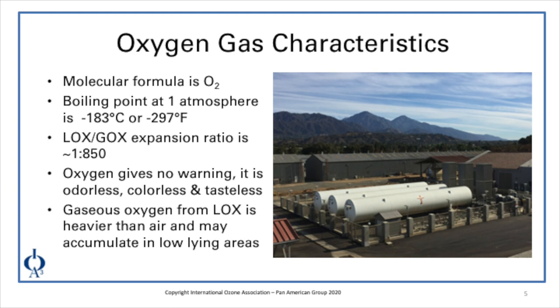As you see on the right, we have large liquid oxygen storage tanks and ambient vaporizers where the conversion from liquid oxygen to gaseous oxygen occurs. Many facilities using a gas diffuser type setup are driven off of the pressure accumulated within those liquid oxygen tanks. With the negative 297 degree Fahrenheit boiling point, that vaporization process of converting from liquid to gaseous oxygen occurs readily through these ambient vaporizers.